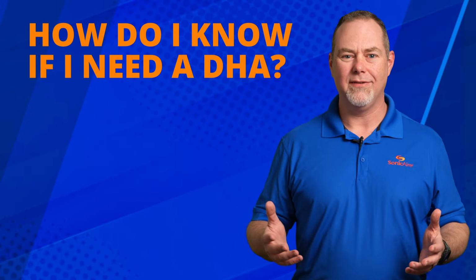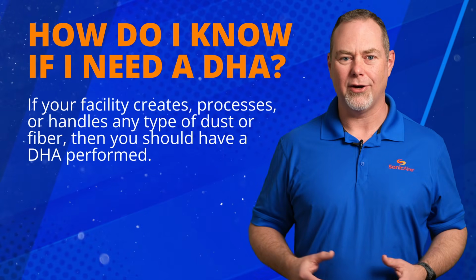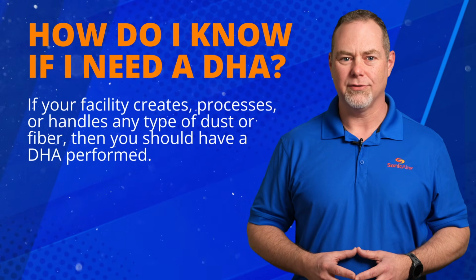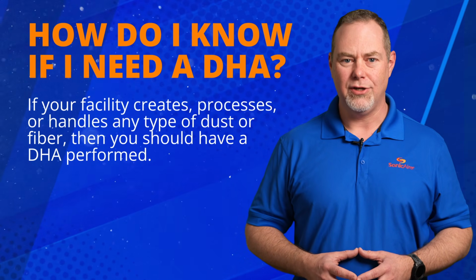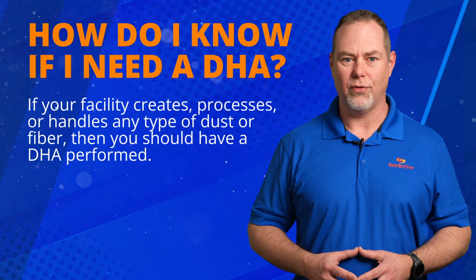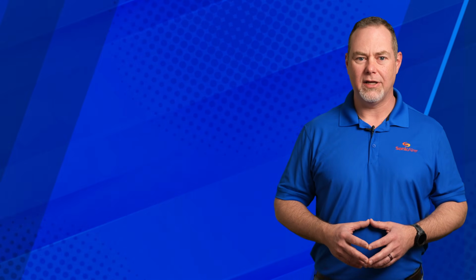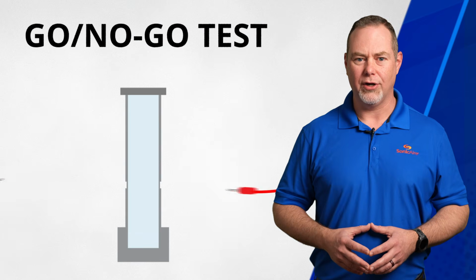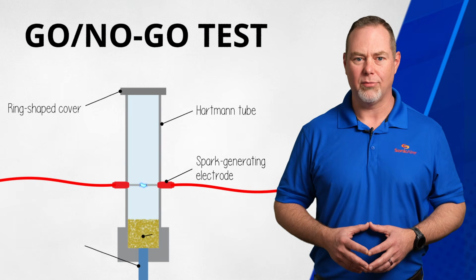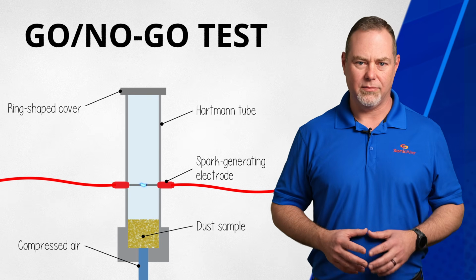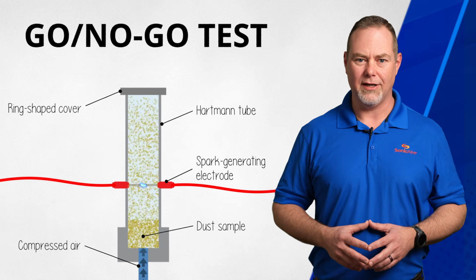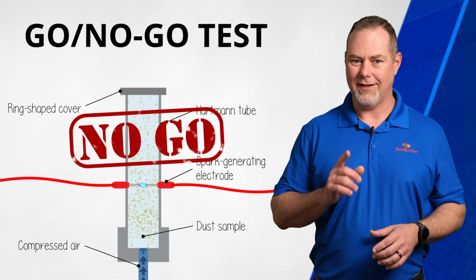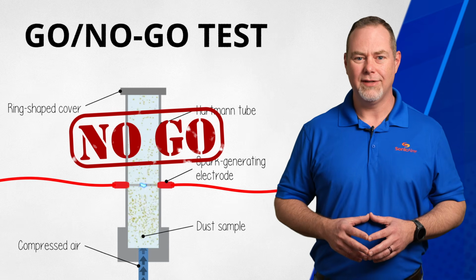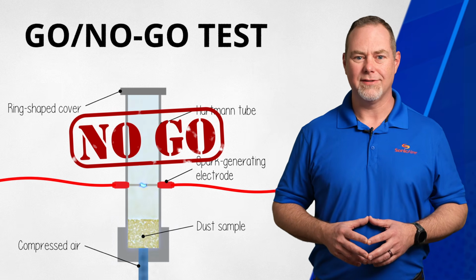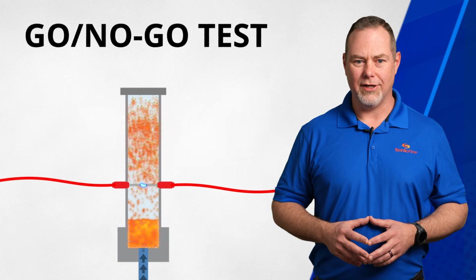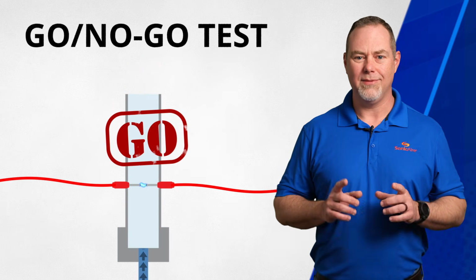So how do you know if you even need a DHA? Well, if your plant creates, processes, or handles any type of dust or fiber, then you should have a dust hazard analysis performed at your facility. The first step in a DHA begins with a go, no-go test performed by an accredited laboratory to determine if your dust is combustible or not. If your dust is found to be non-combustible, then you're in luck. Hang on to this documentation for your records, and you can end your dust hazard analysis there. However, if your dust is combustible, then you need to keep going.